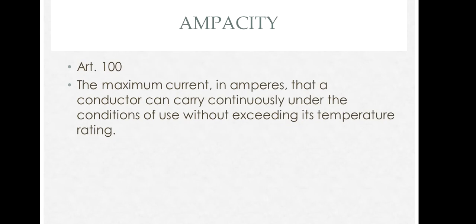There is a definition for ampacity: it is the maximum current in amperes that a conductor can carry under conditions of use without exceeding its temperature rating. The temperature rating is based on the insulation of the conductor. All conductors, depending on their insulation, have different temperature ratings from 60 degrees Celsius to 75 degrees Celsius to 90 degrees Celsius, depending on how the insulation is made and formed around the copper conductor.